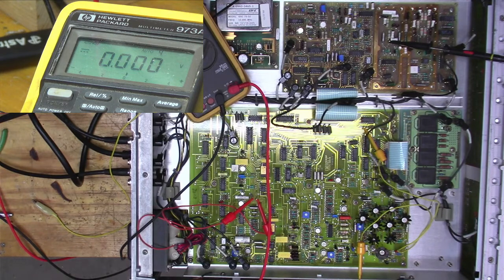So now look, let's say the mixer's output signal leaves the A3 board and enters the A14 board as a current via cable W24. A check of this current is made by connecting AC to ground, move the norm test jumper, right, which we've done, program the front panel to go sine 10 volts, we have, remove cable W24, we have, place an oscilloscope on J24 center connector. The signal should be close to 2 volts peak to peak.